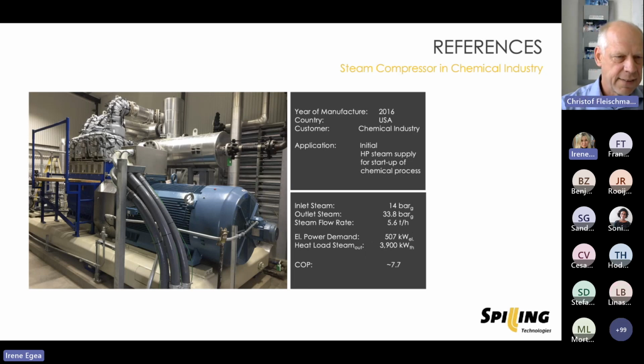Here is also an installation at a chemical plant in the US. This is taken here in the presentation because it shall show that this also works on higher pressure levels. Here on the inlet side we have about 14 bar gauge, and on the outlet side 34 bar gauge. And since we are with the inlet steam temperature and the outlet steam temperature at quite high temperature levels, we have to do the steam compression a little more carefully.